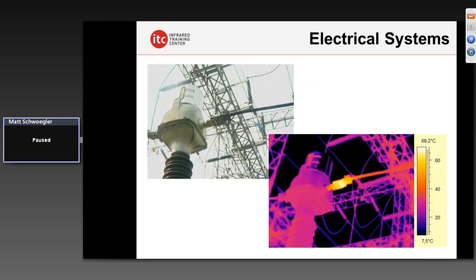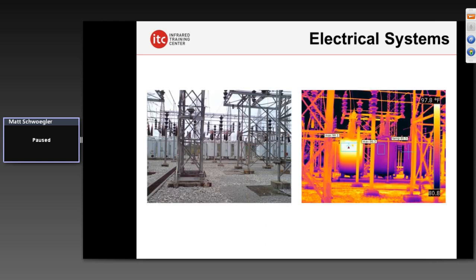In outdoor substations, IR has been utilized very successfully for decades to find high-resistance connections on bushings, bolted connections, lightning arresters — you name it. Infrared used very successfully to find these thermal differences. Here we have oil-filled circuit breakers in this outdoor substation. You notice the A-phase tank appears to be warmer on the surface than the other two, indicating a thermal anomaly is occurring.